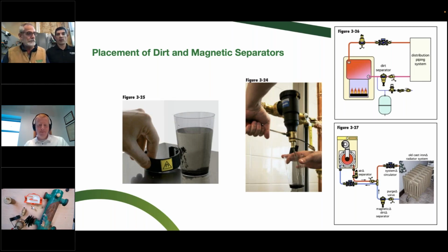Yeah, if you continue to get buckets of magnetite weeks and months into a system, the underlying issue is probably an air issue. It could be, with these big radiators, that you're just slowly bringing some more debris back from the bottom of those radiators that's collected. But if you have a bunch of magnetite every single time you blow down a separator, it's an indication of air that you have to address somewhere else.